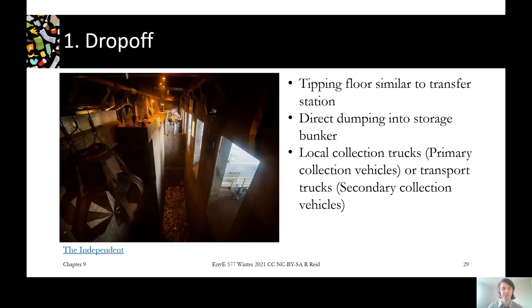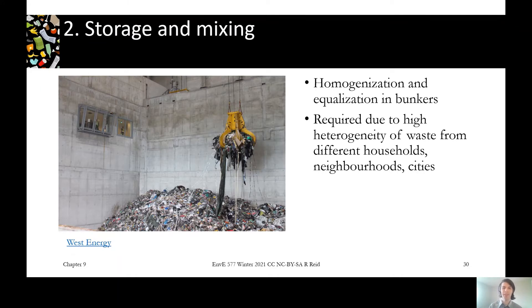The drop-off step looks similar to other waste facilities like transfer stations, AD tip floors, and MRF tip floors — just a place for trucks to come in and drop waste off. What's special about thermal treatment facilities is how important it is for the waste to be fairly homogenous and fit within the design composition parameters. So at this stage, there's a storage and mixing element. You can have ICI waste and curbside waste from different communities, so you want to homogenize as much as possible to keep the reaction stable and easy to control. The waste is equalized by being mixed before being charged into the combustion chamber.